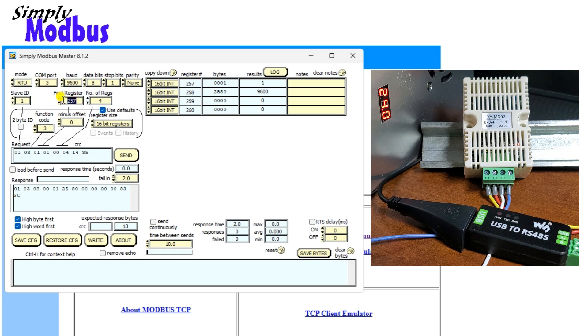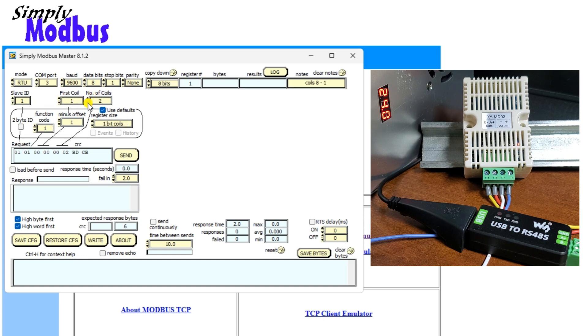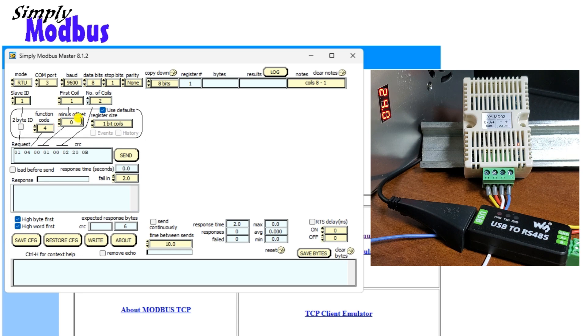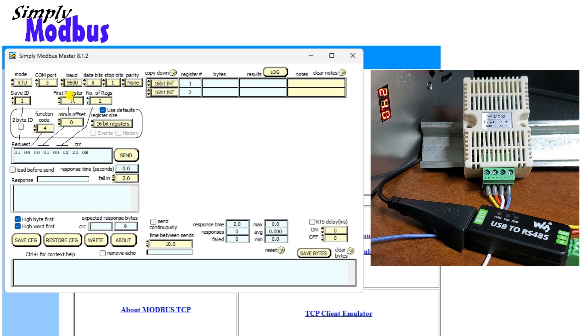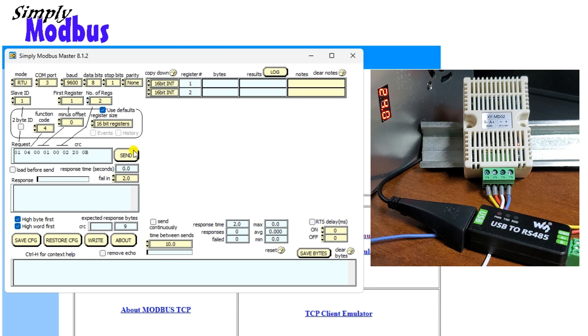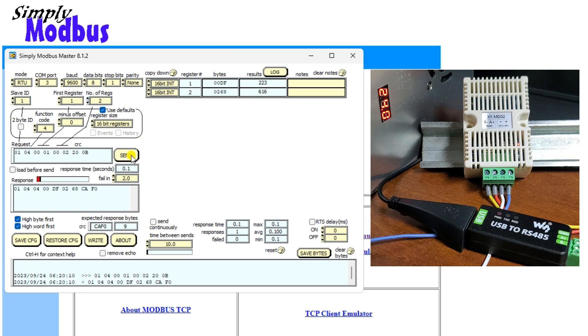Here is the Simply Modbus 8.1.2 interface. The first thing that we will do is read the temperature and humidity. Modbus RTU will be the mode for this communication. Comport 3 is used in our example based on the device manager indication. Our slave or server address is 1 and we will read two registers starting at address 1. The Modbus function code will be 4 with an offset of 0 for the address. 16-bit registers will be read. Once we select the send button, our returning data can be seen in the results.